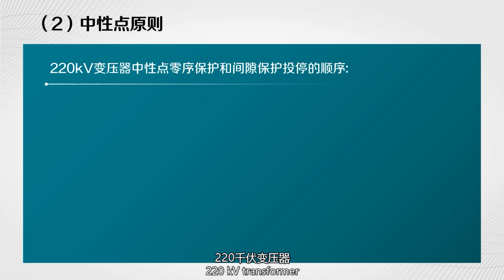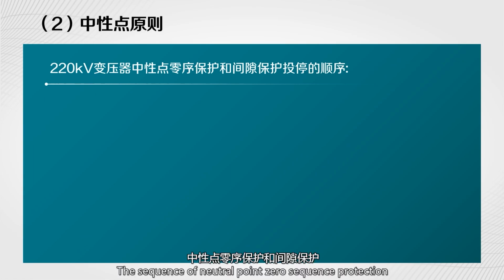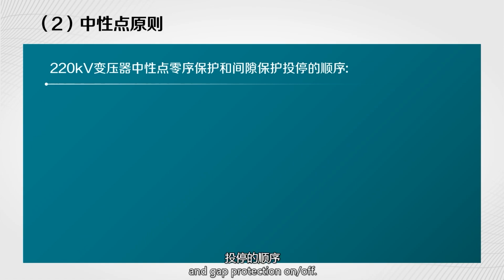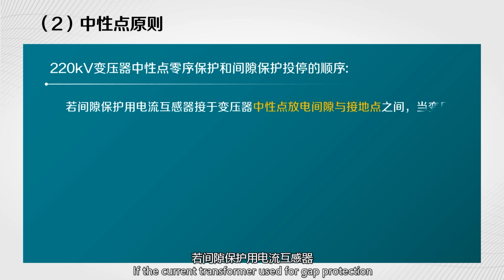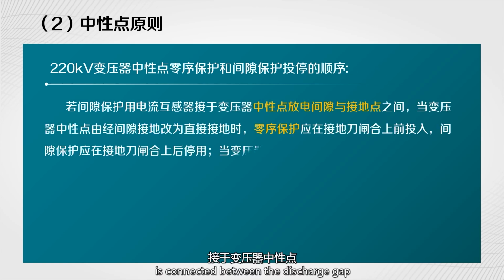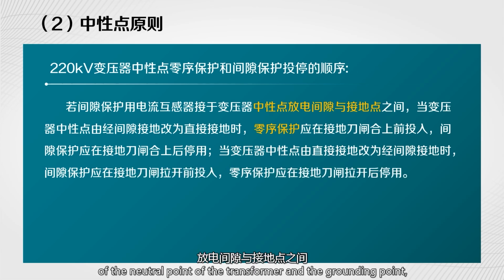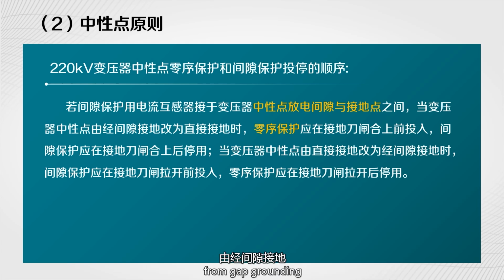220 kilovolt transformer: the sequence of neutral point zero sequence protection and gap protection on/off. If the current transformer used for gap protection is connected between the discharge gap of the neutral point of the transformer and the grounding point, and the neutral point of the transformer is changed from gap grounding to direct grounding, the zero sequence protection should be activated before the grounding switch is closed, and the gap protection should be deactivated after the grounding switch is closed.